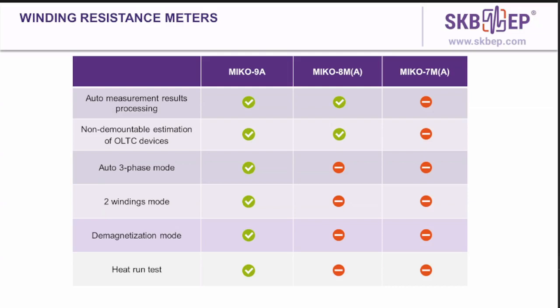They are auto measurement results processing. It calculates the relative deviations of three-phase winding resistance between each other. It can convert the linear resistance into phase resistance. Non-demountable estimation of OLTC devices. It allows to perform the express diagnostics of the state of the transformer OLTC.